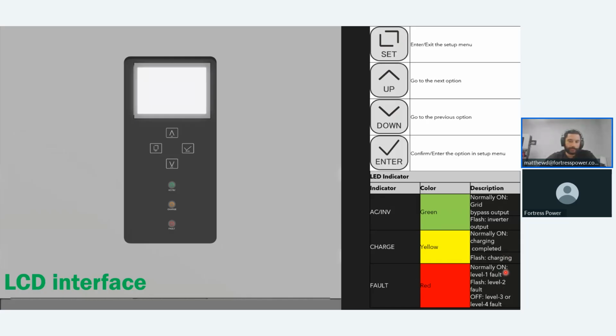Then you have charge, which is in yellow, assuming that it is charging. You would see it flashing. When it finishes charging the batteries, then you would see it on a solid status. And then fault, we have levels of fault. Level 1, which is the less severe, right? I'm sorry, the more severe. That would indicate fault. It would always be on. Flashing would be level 2, which would be less severe, and then off, level 3 or level 4.